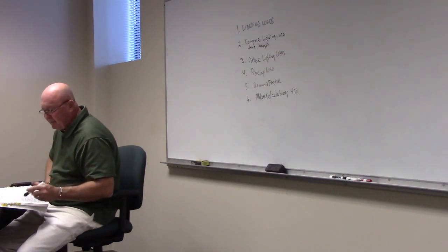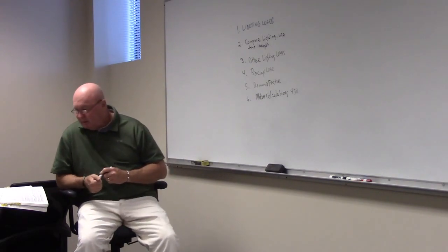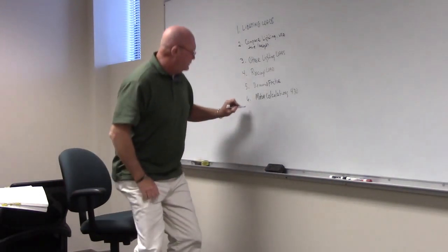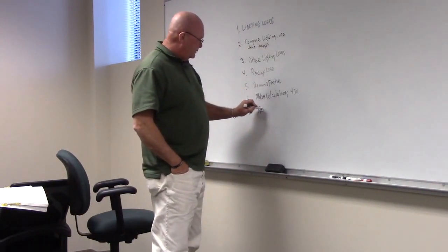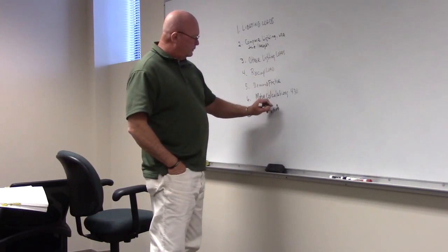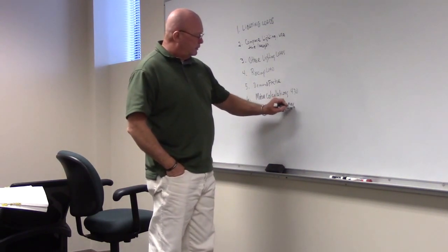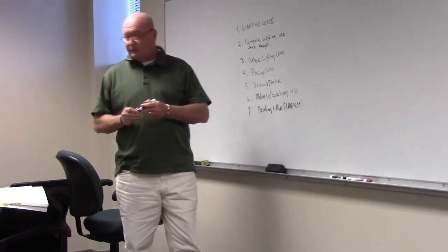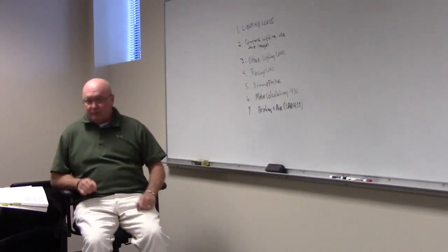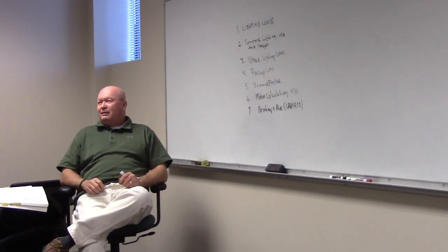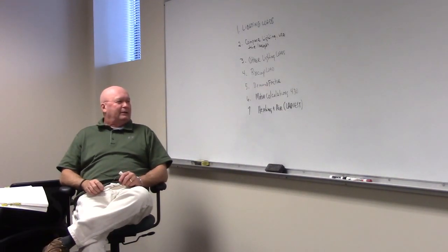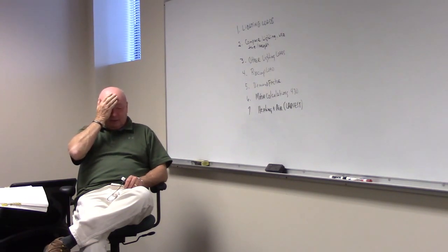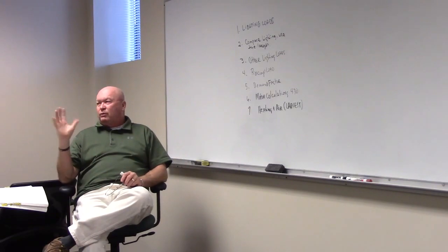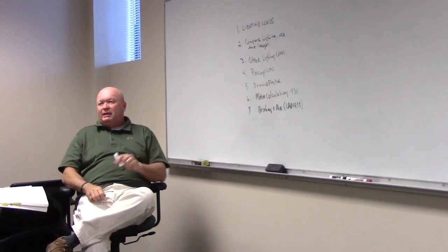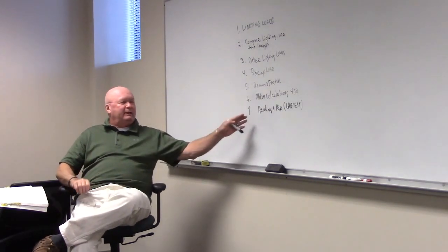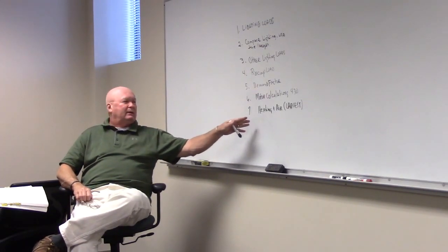Okay, so that's step 5. Step 6. Step 7, what are we doing? What does it say? Somebody read step number 7. Calculate both the heating and air conditioning loads and use only the largest of the 2 in the total load calculation. Yeah, largest. Why just the largest? Why not both? Unless you got kids, you only run them one at a time. That's right. You'd have to have a pretty sophisticated system to run both of them at the same time. And there are a few little quirks we're not going to get into tonight, like if you got supplemental heating, it's a little different. But generally speaking, 99% of the time, most people's houses, it's the larger of the 2.